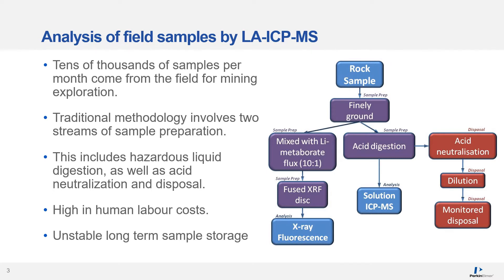In these cases, the spectrometer does provide a very stable result in data coming from the system. However, this depends on a lengthy process of digestion using acids, which in some cases may not dissolve all the elements in the method to the same degree. This digestion relies on the operator to identify issues with the digestion or precipitates in the vessel.